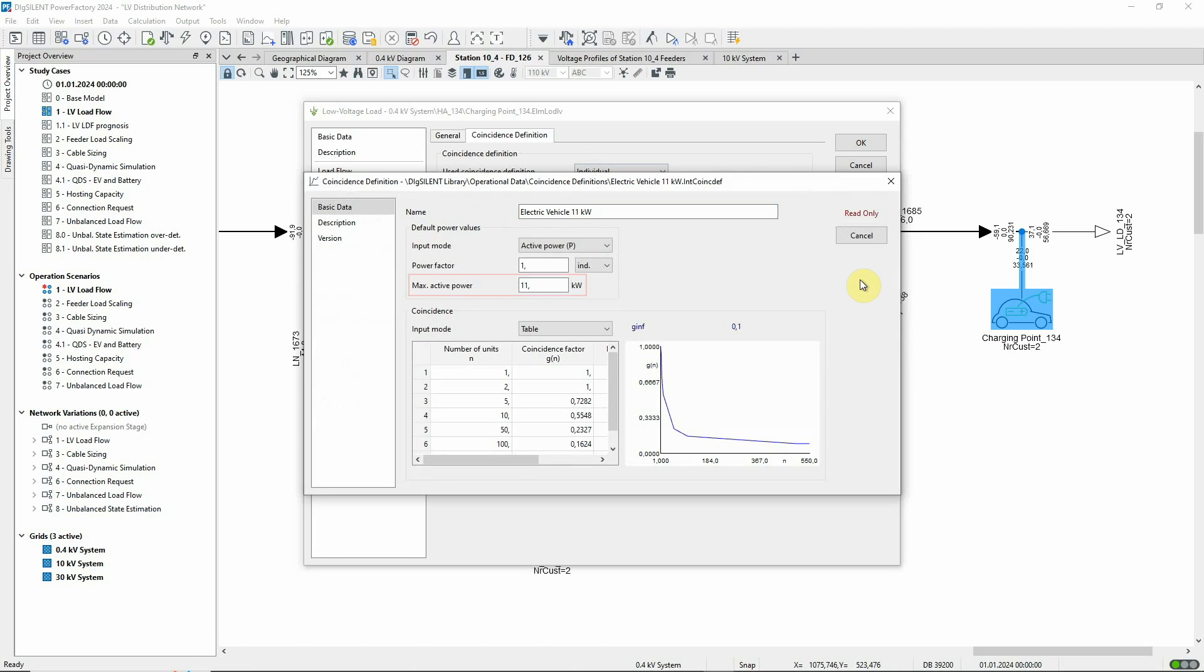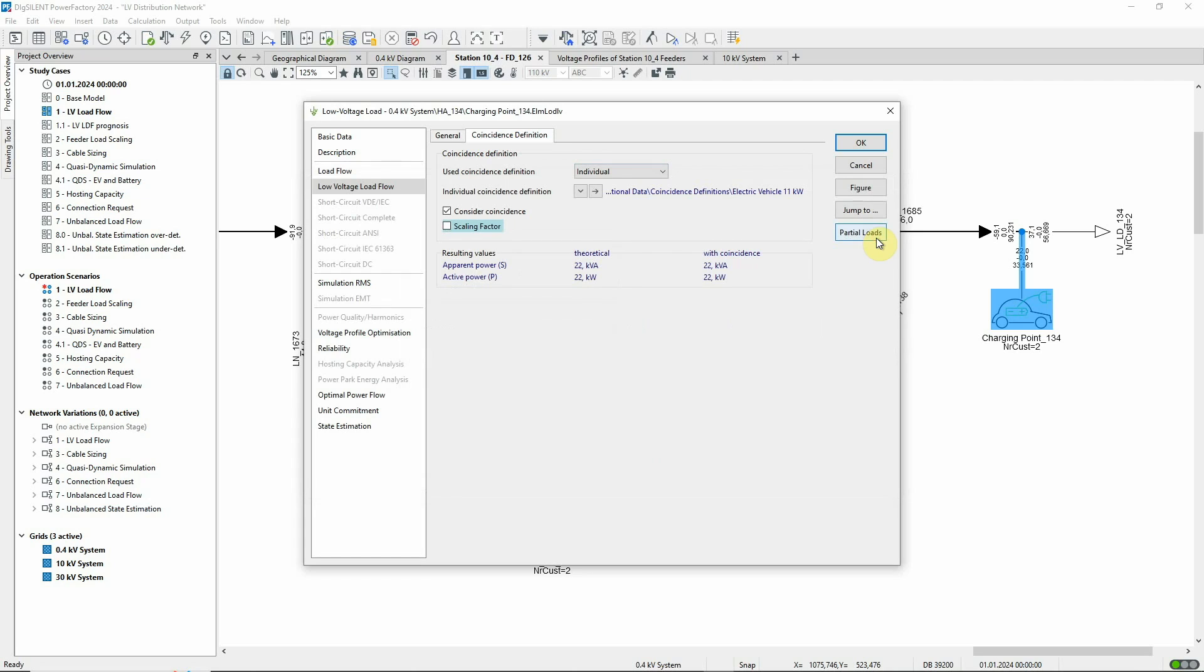This curve represents 11 kilowatt charging points and accounts for the duration of the charging procedure. Note that the reduction in coincidence is only applied for numbers of units greater than two.